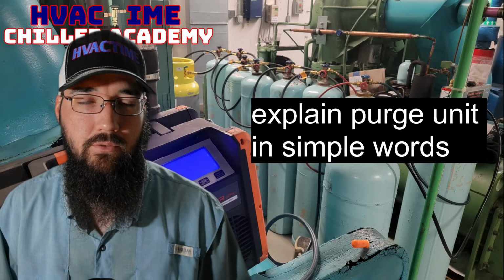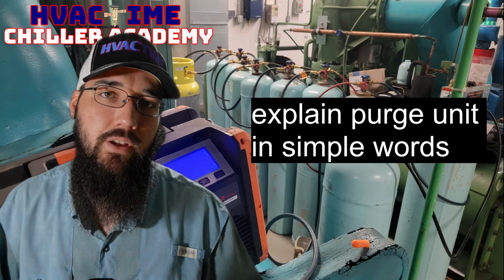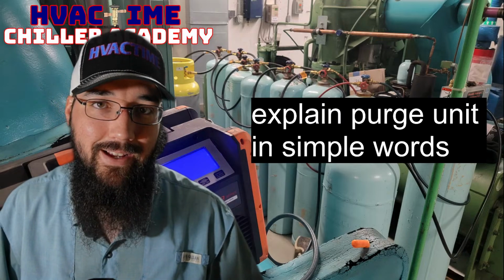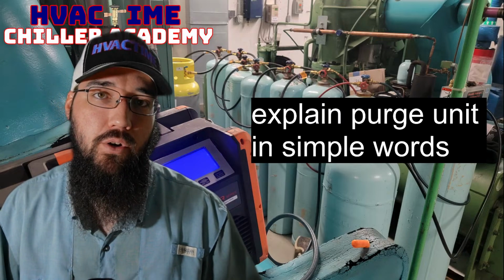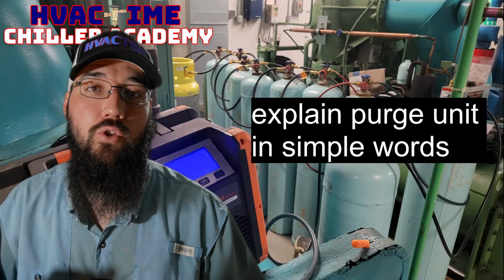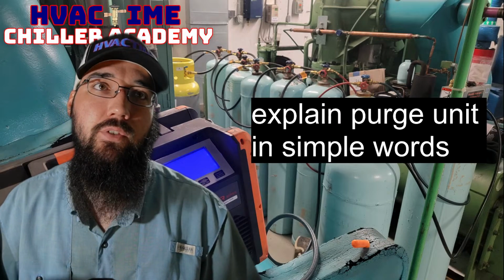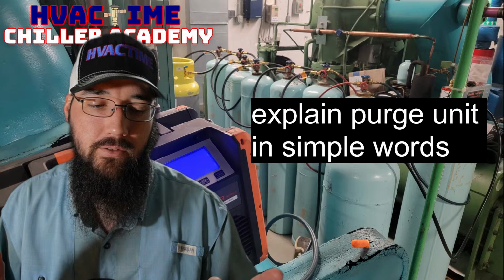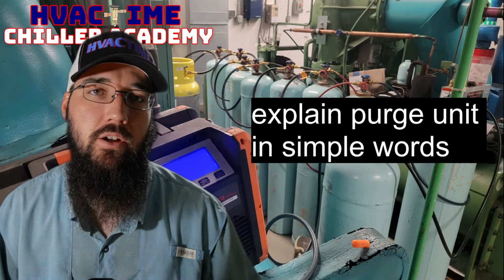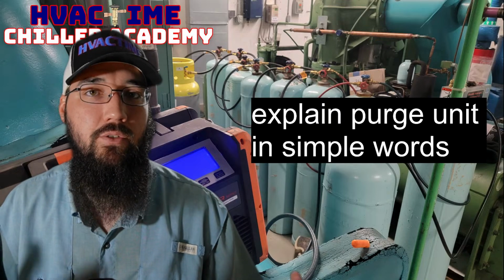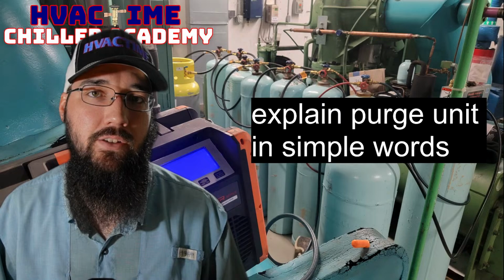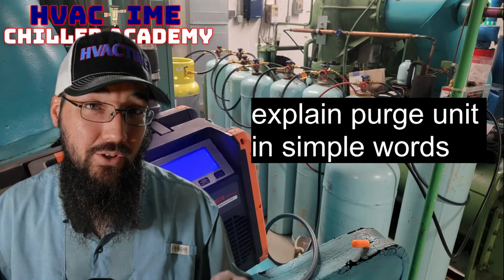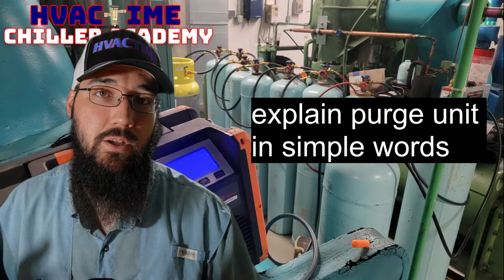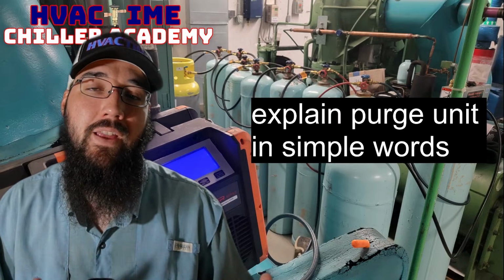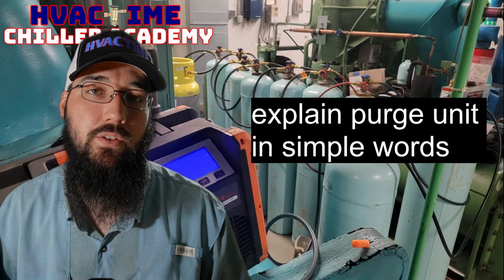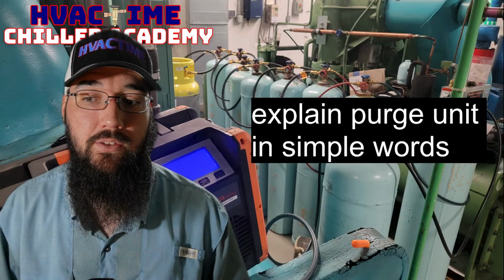If you're doing a low pressure recovery, something to consider is having a portable purge, and they make these. Ref Tech has a portable purge unit that you can hook up and use during a low pressure recovery. This is just a good safe procedure to do, whether you think you have non-condensable issues or not. During the recovery phase, there is a lot of opportunity for non-condensables to get into the system, and we aren't going to want that in there, especially if we're going to reuse that refrigerant later to get that machine back online. And we don't want to be in a position where at startup we're trying to mitigate non-condensables in the system that may have just happened during the transfer phase of things.